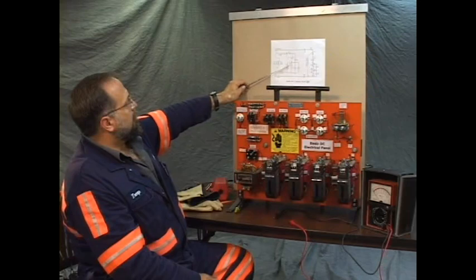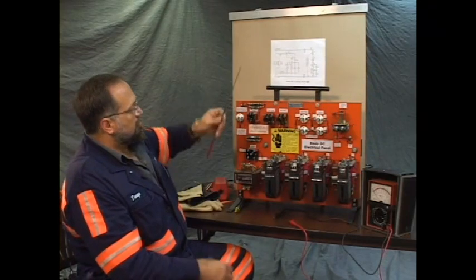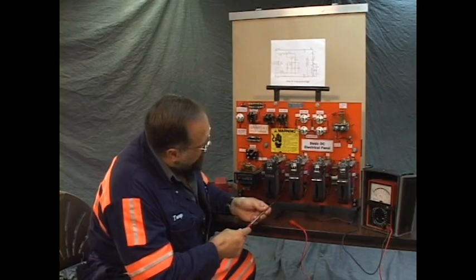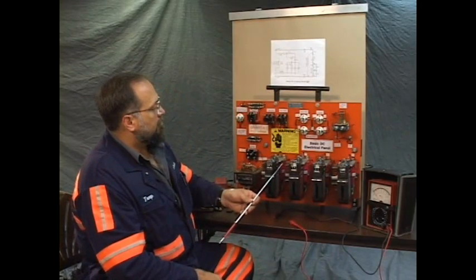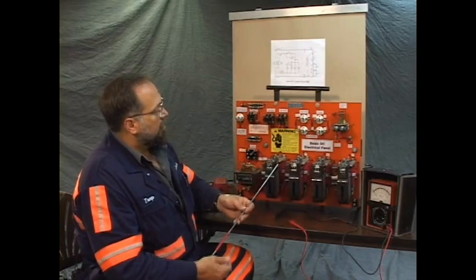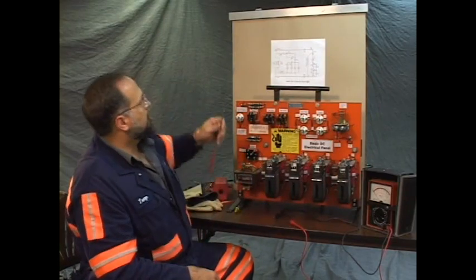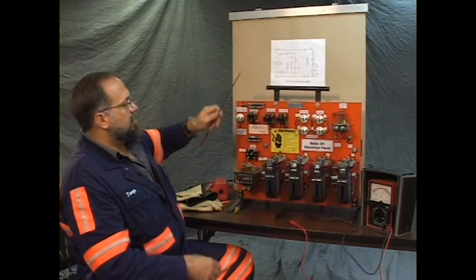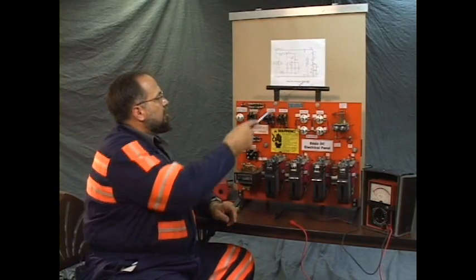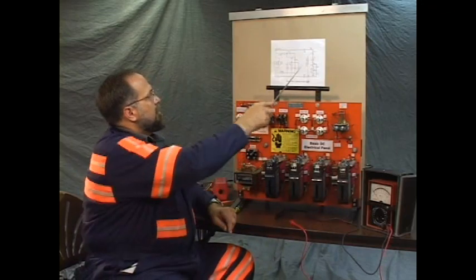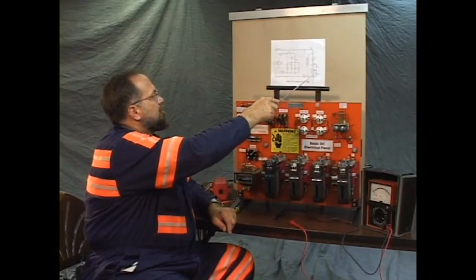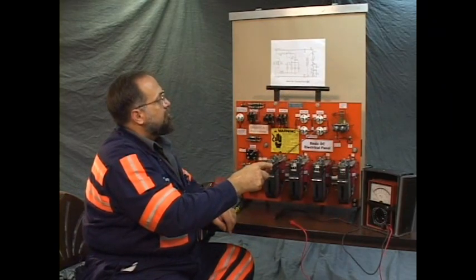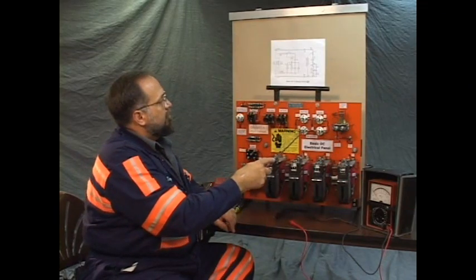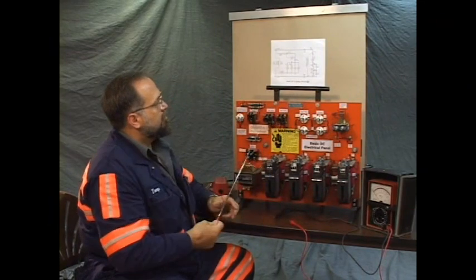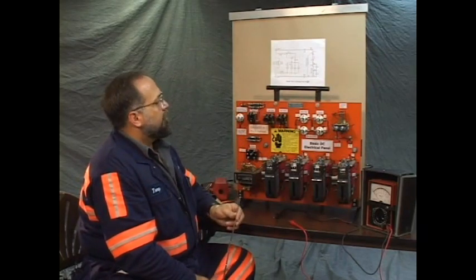When 1A mercury tube times, it has magnetism transferred by this little lever to the bottom of the mercury tube, and after the interval passes, contact is made, and the 2A coil receives power. This coil here receives power. Its contact tips are closed right here. When 2A contact tips are closed, the current has a path around that resistance and no longer has to pass through the resistance from R2 to R3. This light will go off. This light will become very bright as the shunt field light. And the motor's running at full speed.